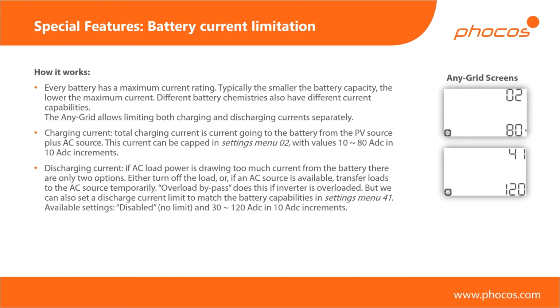I think what's more interesting is if you have an AC source. For example, if you do have a grid connection, then this is very similar to the overload bypass I discussed before, where if you're demanding more power than the inverter can deliver, it will automatically switch to the grid temporarily. The same thing will happen here, except now you can decide at what discharge current that happens. Before it was just a pure power thing, where if you exceeded the nominal power of the unit, it would switch to the grid. In this case, let's take the same 40 amps, for example. My battery can only handle 40 amp discharge current. Then in settings menu number 41, you can just set that up.